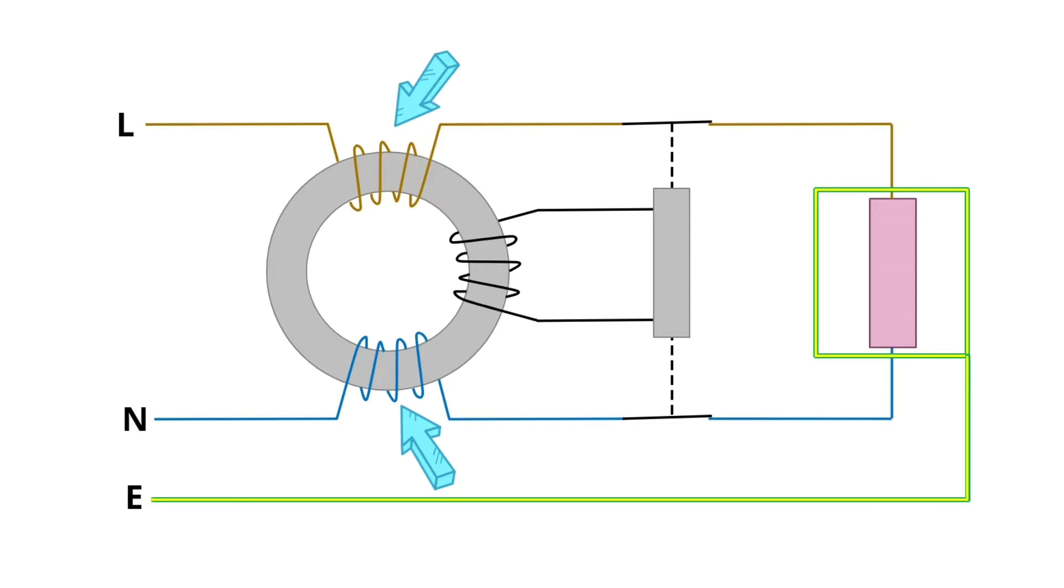Now, at the same time, wrapped around the core, there's this third coil that feeds a tripping device that connects to the switching contacts in the line and neutral connections. Now, when the circuit is healthy, the current passes through the line, and the same amount of current comes back down the neutral.